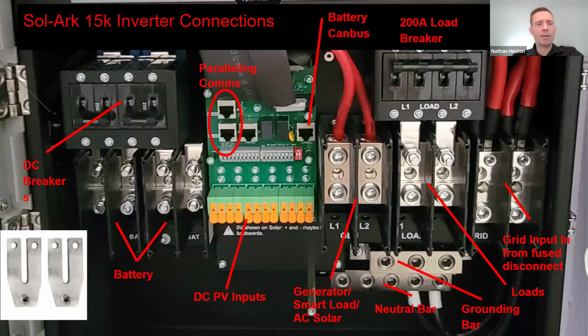So let me highlight some of the connections here. If you've not seen the inside of a Sol-Ark 15k, there's a lot of working room inside. It's fairly nice to work within this unit because there's a lot of room to run your wires, to run your cabling. So I'm going to point out the main parts. First off, people are sometimes confused by the fact that there are two 200 amp breakers inside the Sol-Ark 15k. These are here so that you can protect your 2-aught wiring coming from battery banks. So you can use two sets of 2-aught wiring and utilize those 200 amp breakers. You could have two independent sets of 2-aught wiring coming into the batteries to the bank independently, and use this battery connection as a combiner.